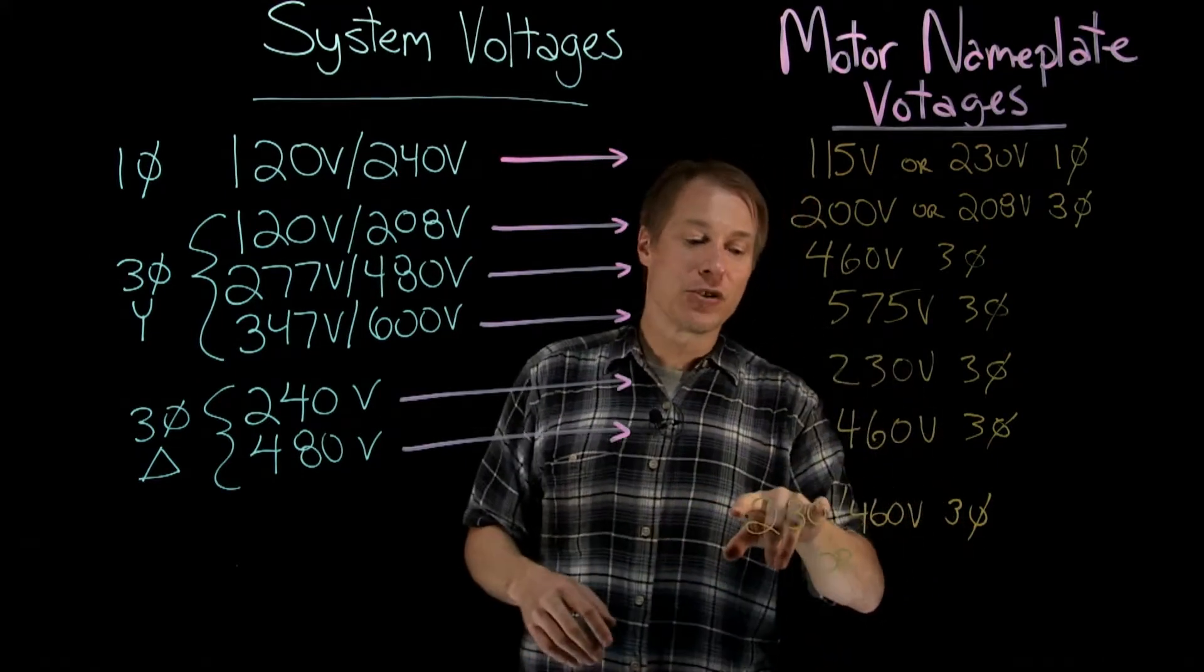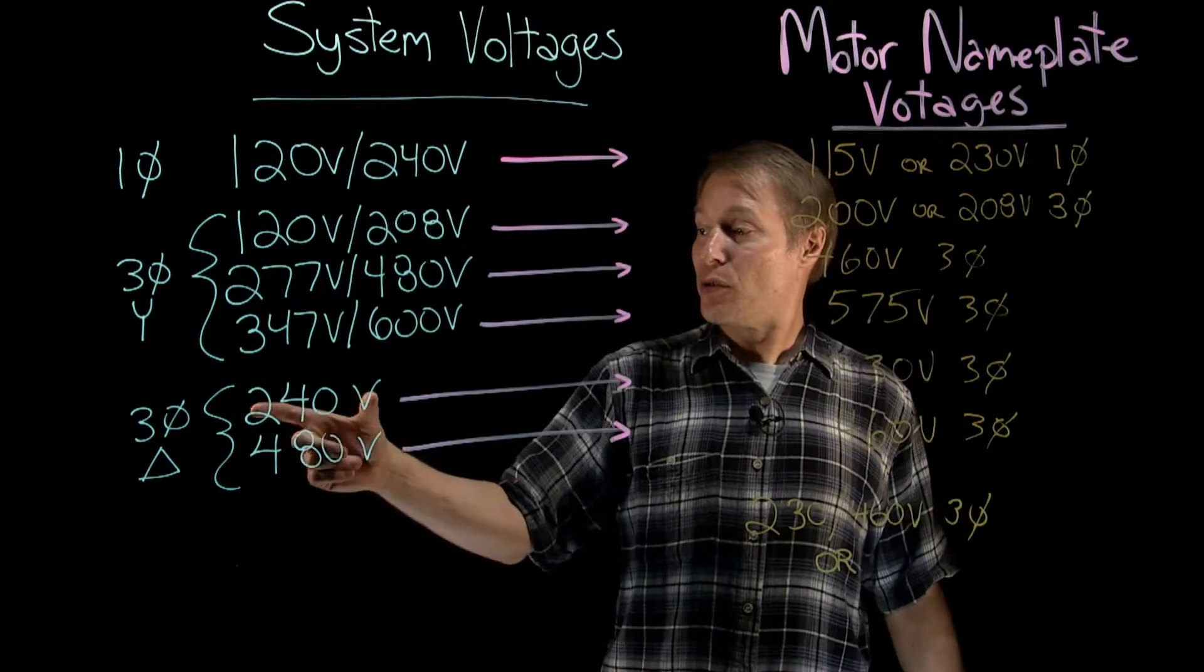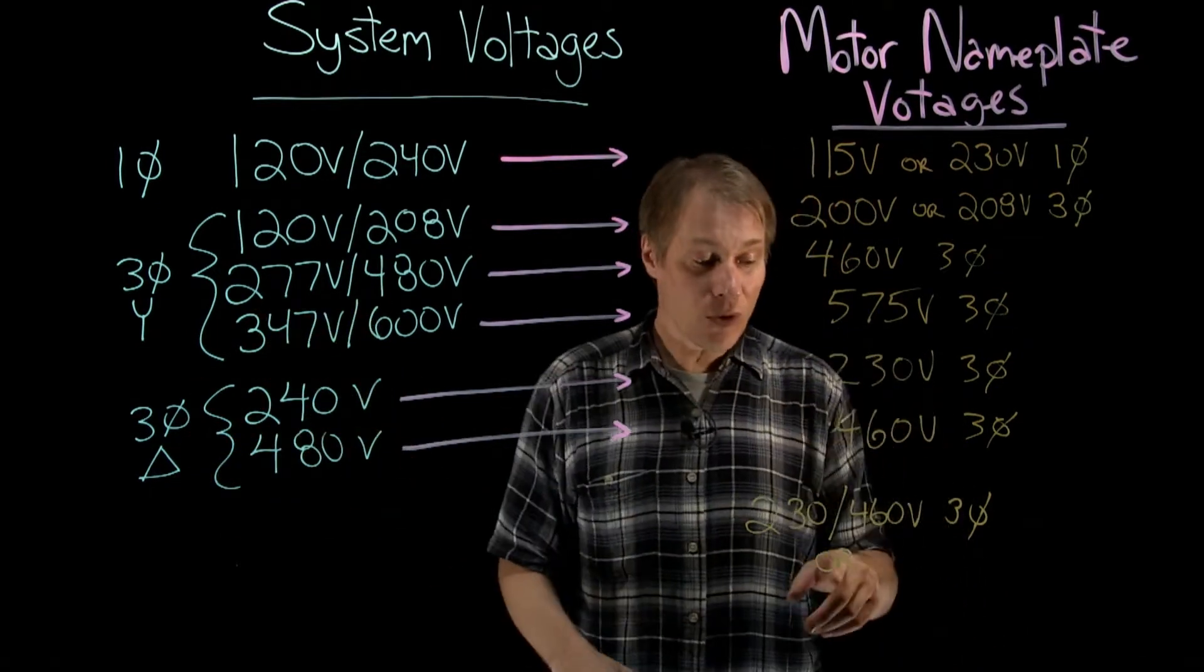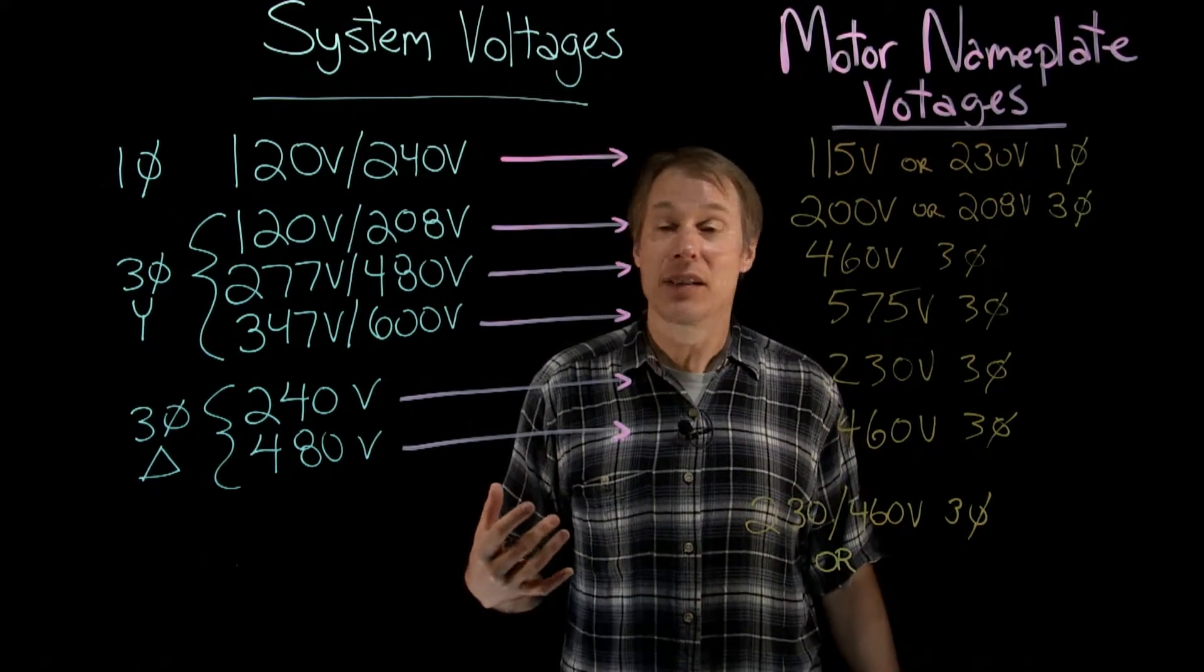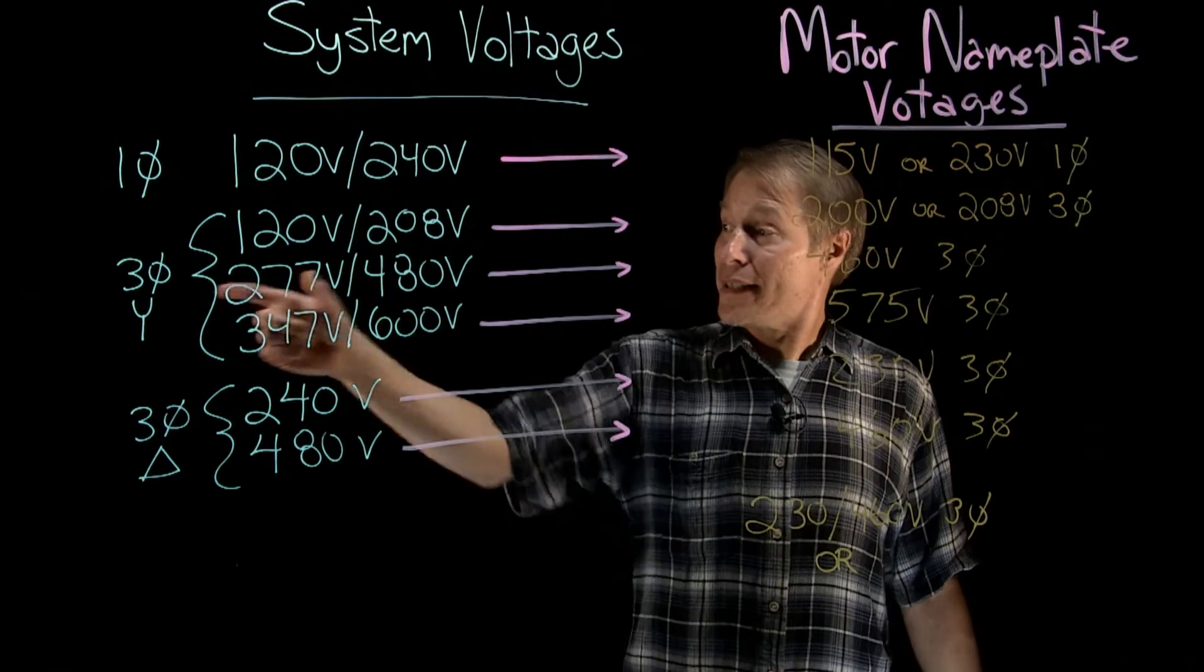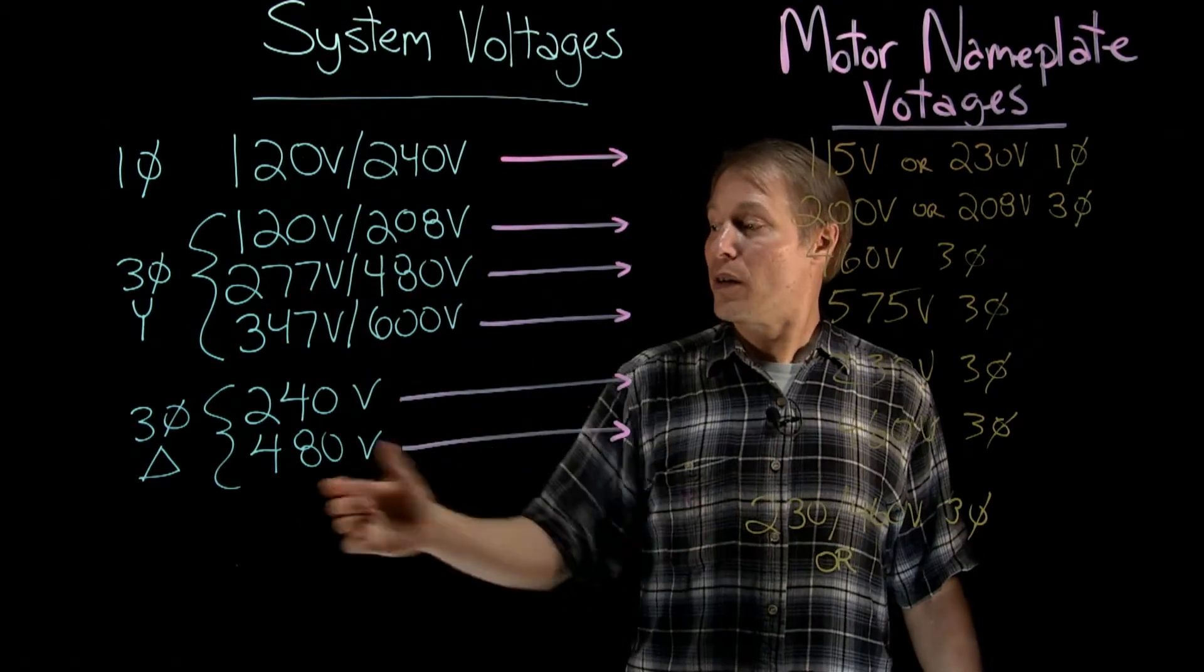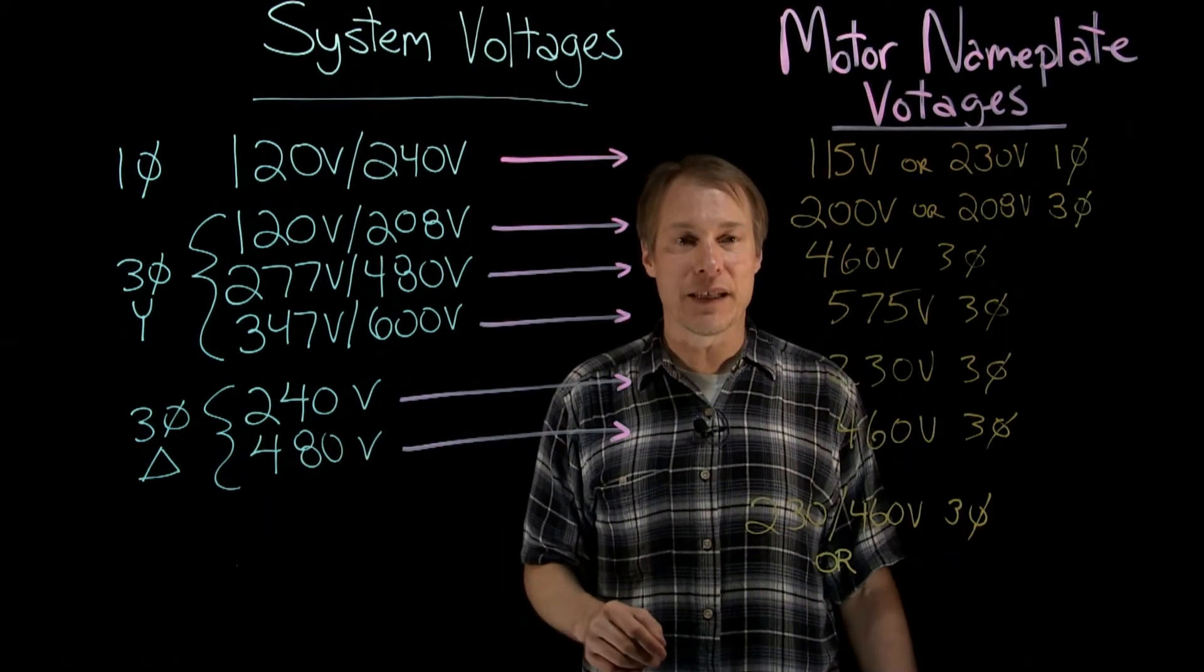So if you connect it as a 230V motor, you can see your option here would be then for the 240V three phase delta supply. If you connected it as a 460V motor, you have two options. You can connect it to the Y system, the 277V/480V system or the delta system which also supplies 480V three phase.